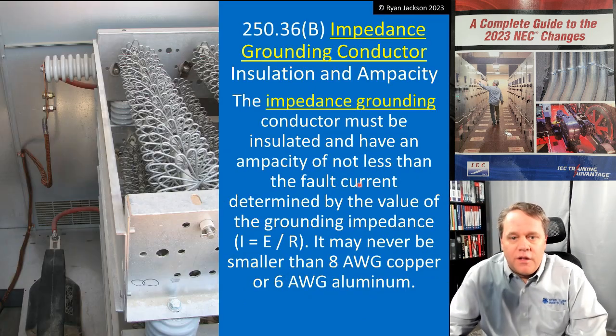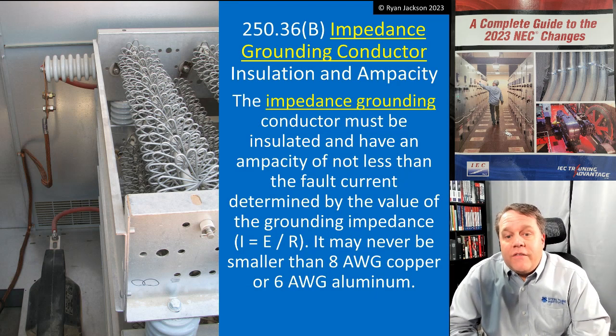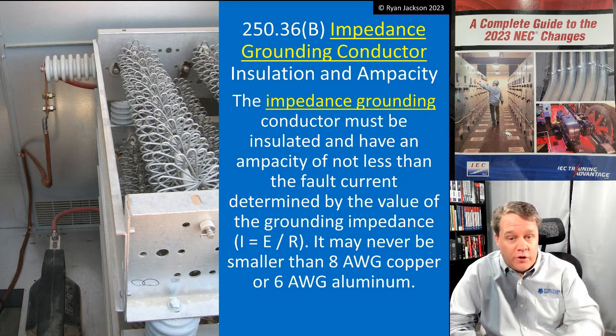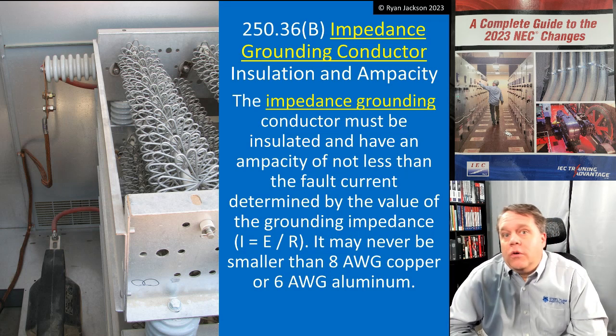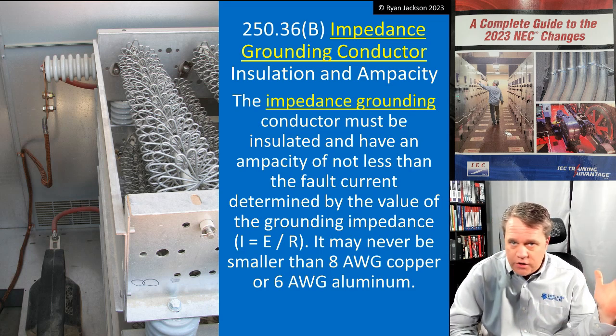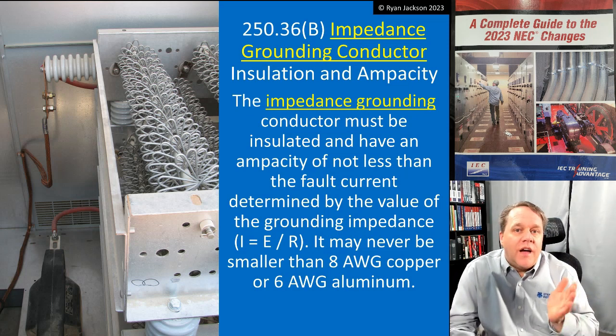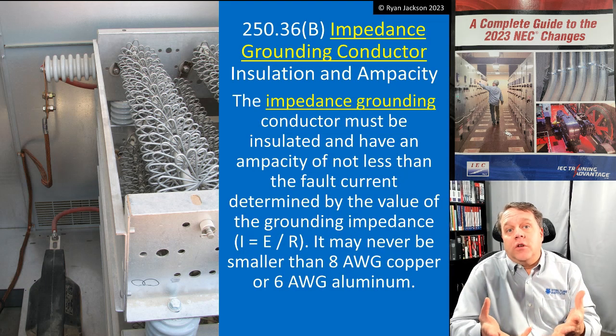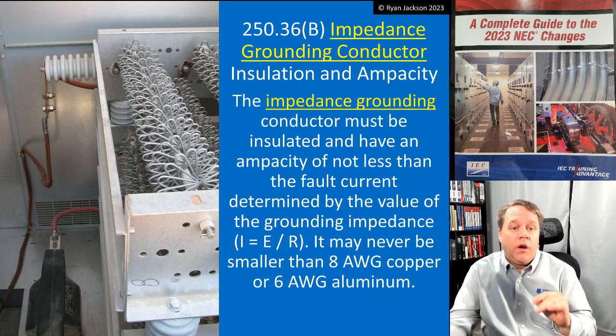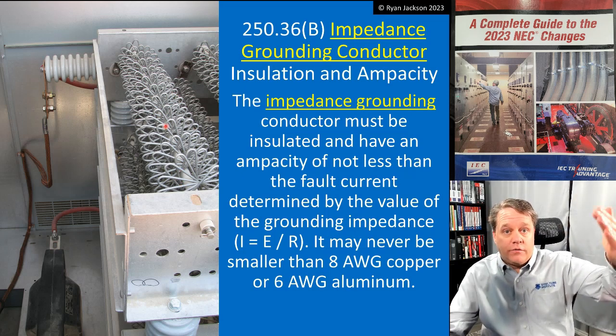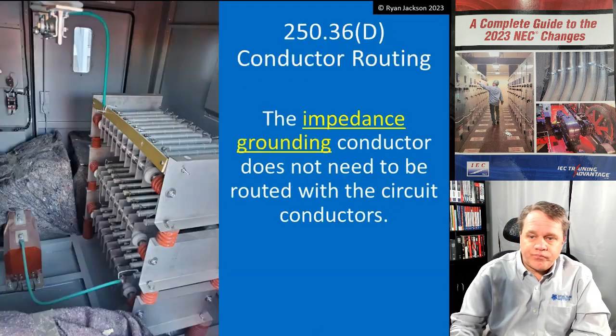The impedance grounding conductor must have an ampacity of not less than the fault current, which is determined by the value of the grounding impedance using I = E/R. It must never be smaller than 8 AWG copper or 6 AWG aluminum. Just like service conductors and grounded conductors, we have a minimum here - it can't be 14 AWG. We size it based on the amount of fault current it's expected to see: line-to-ground voltage divided by the resistance of the resistor gives us the ground fault current.